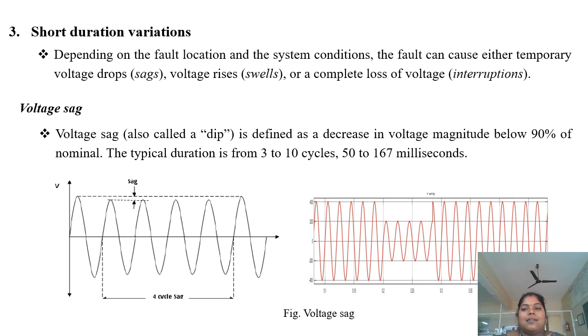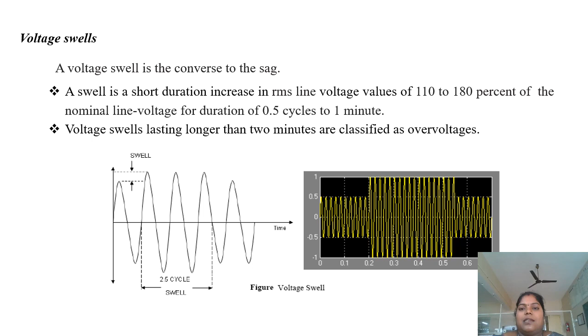Next, voltage swell. Voltage swell is a short duration increase in RMS line voltage value of 110% to 180% of nominal line voltage for a duration of 0.5 cycles to 1 minute. Voltage swells lasting longer than 2 minutes are classified as over voltages. Next, interruptions. Interruption is nothing but the supply voltage or load current decreasing to less than 0.1 per unit for a period of time not exceeding 1 minute. It is classified into momentary, temporary or long term.